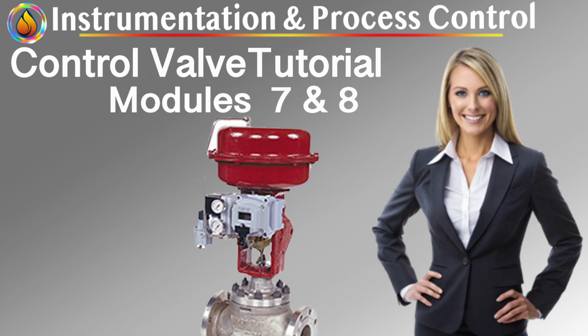Positioner technologies. Pneumatic positioners. Purely pneumatic positioners operate using force balance principles. Characteristics: mechanical feedback via cams or levers, no electronics, rugged and intrinsically safe, limited tuning flexibility. Strengths: reliable in harsh environments, simple troubleshooting, immune to electrical noise. Limitations: limited dynamic adjustment, lower resolution, manual calibration required. They perform well in steady, slow processes, but struggle in modern high-performance control environments.